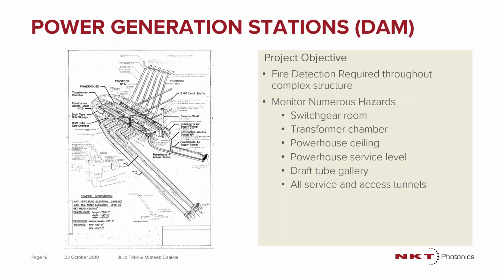On the same controller and with the same cable, you can run the cable in the switch room, switchgear room, transformer chambers, powerhouse ceilings, powerhouse service levels. There are many tunnels also leading to different areas of a facility. So the ability to run that same fiber optic cable, pinpoint exactly where the area of interest is, zone it accordingly from a virtual point of view and set different alarm parameters for every single asset is where we see fiber optic linear detection being different from traditional linear detection.